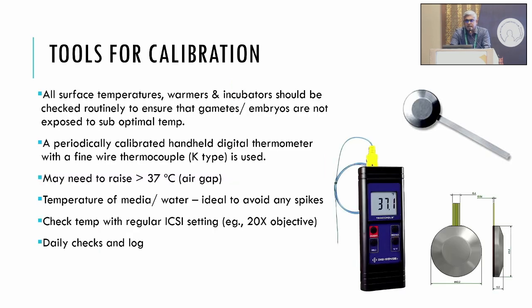The most widely used QC tool for temperature is the thermocouple, which you see in the picture. But it should be periodically calibrated. It's very important. It should be calibrated at least once a year. Many of us depend on engineers who come to do the external audit and the QC. But we should make sure that they also calibrate their equipment. We take it for granted that they do it.